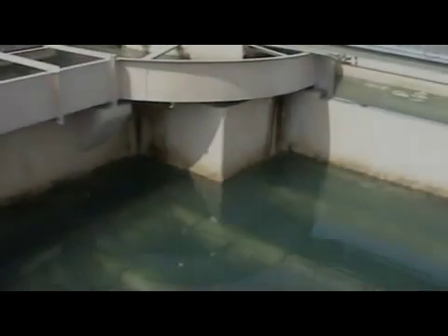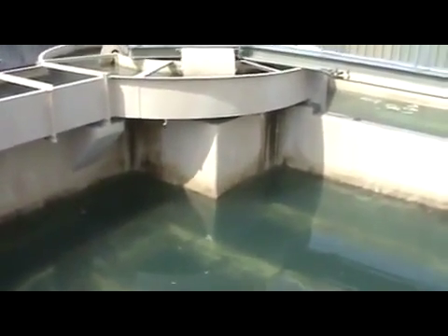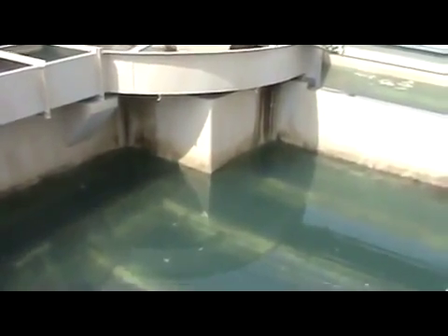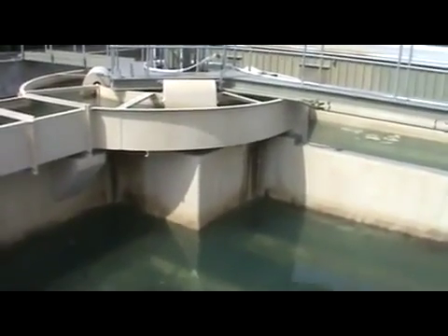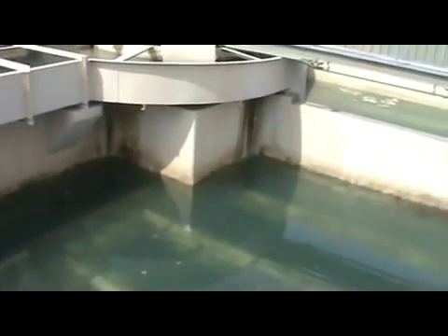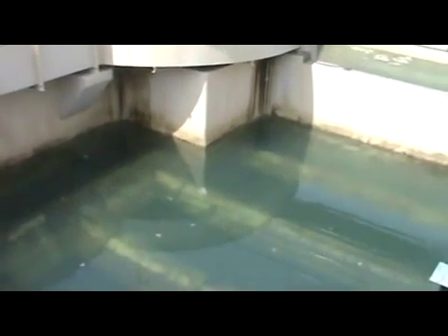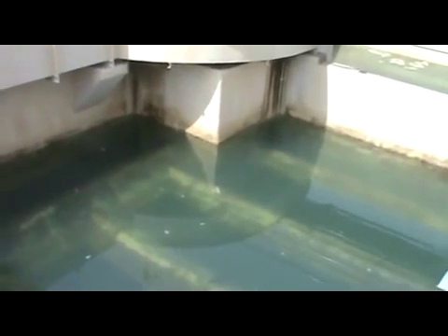When we backwash a filter bed, basically what happens is, first off, the inlet to the filter bed is closed. The effluent side of the filter bed is closed. I should say by inlet, meaning that connection is broken so water's not flowing into it. The effluent valve is closed, and you go through what's called a drain period, where you drain down the water. The water drains to a wash water collection tank.